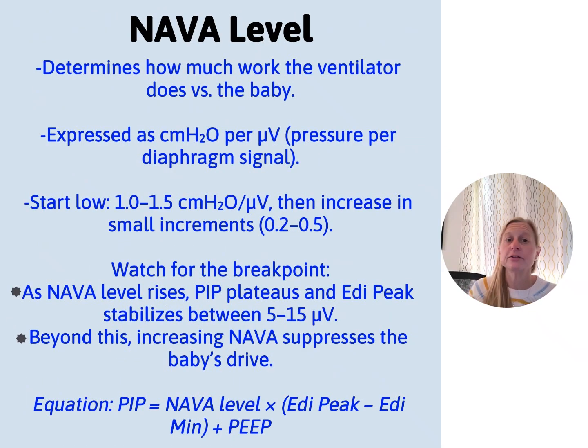The NAVA level determines how much work the ventilator does versus the baby. So essentially, as a NICU nurse, I think that's just what you need to know is the higher the number, the more work the ventilator is doing. Like that's the easiest way to kind of bring this to you. It's expressed as centimeters of water per microvolt. Again, that's just like a number that I'm just like, okay, just tell me what I need to know. We're going to start low, maybe start around 1, 1.5, and watch as we go up.